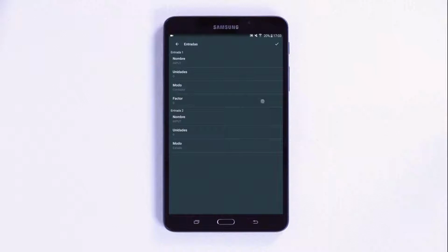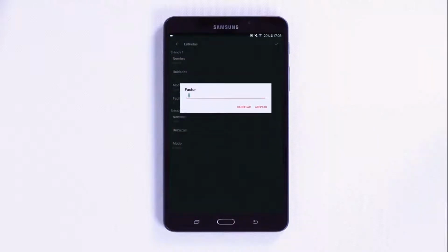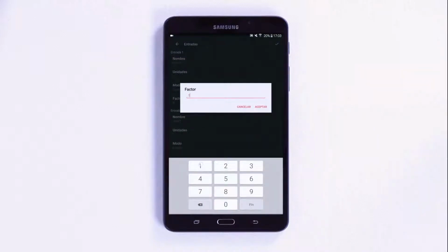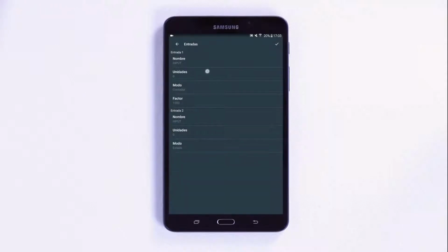For example, if a water meter has a pulse probe with a conversion rate of 1,000 pulses per cubic meter of water, or liters, this will be the value that will be programmed by associating the cubic meter or liter variable with the input's value.